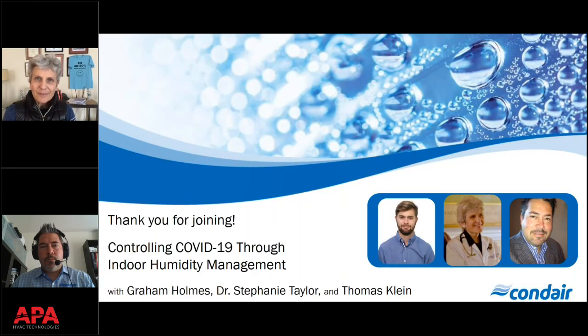So sometimes if you don't have good R-value windows or you have any sort of thermal bridge, you can see condensation. But it's not a reason to just a priori crank the humidity down to 20% or turn your humidifier off. It needs to be managed. In certain cases, like a large building, we've seen owners implement something like an air curtain in front of the windows to bring a different temperature of air to the windows area. So if you had a commercial building with an atrium that had condensing happening, it can be worked around through design. It does take planning, but it can be worked around. We've seen that before.